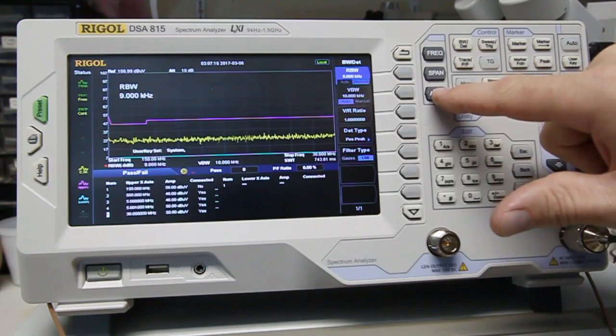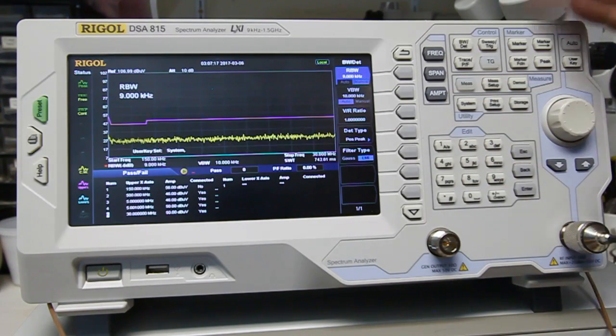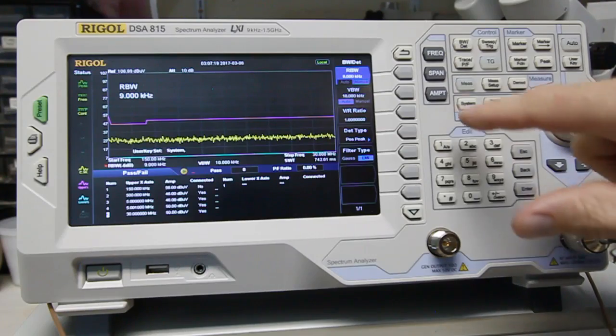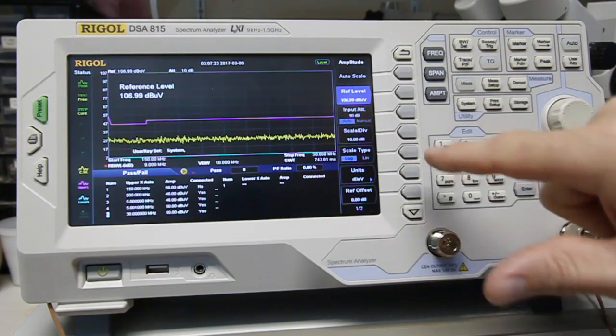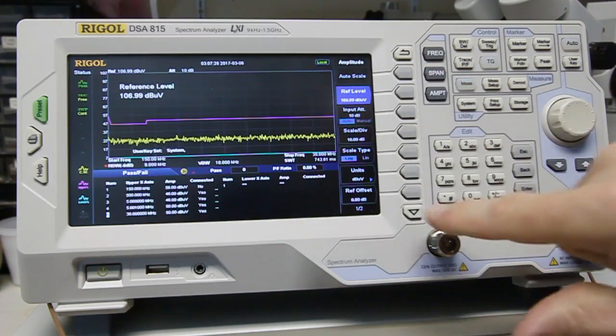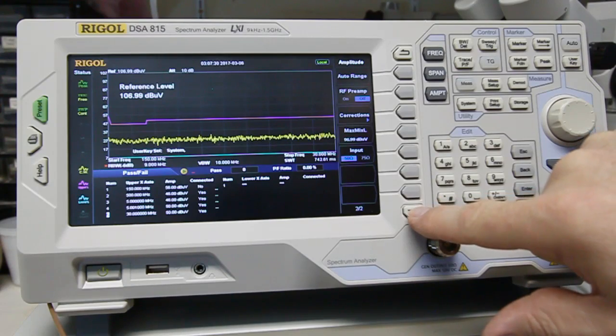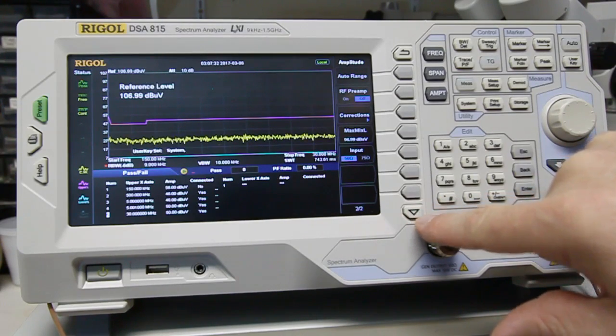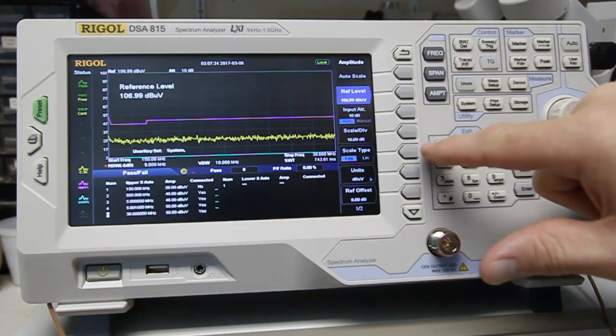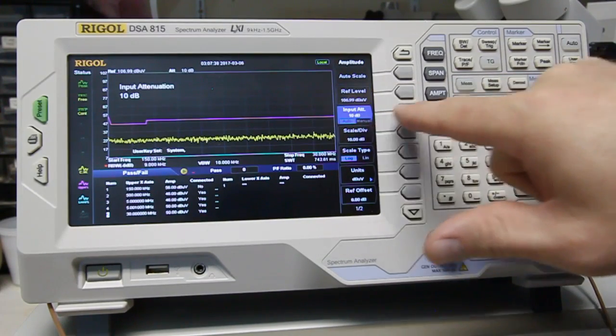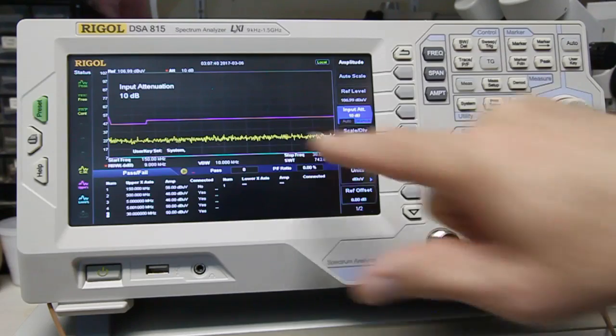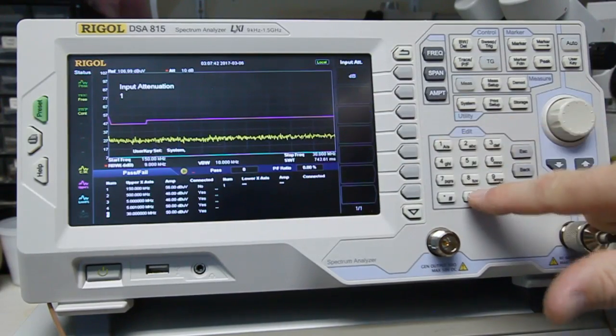Next thing is we want to make sure that we have an attenuator turned on in the analyzer for safety purposes. You can already see that it's turned on here. Input attenuator, we're going to go to manual. And it's already set there. But we're going to put in 10 dB.